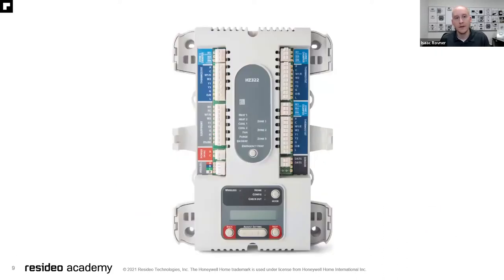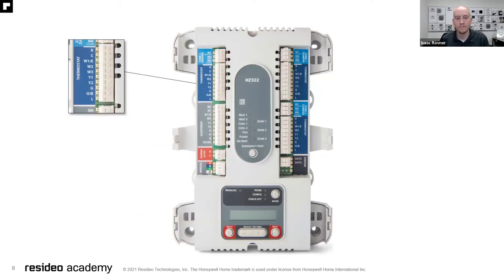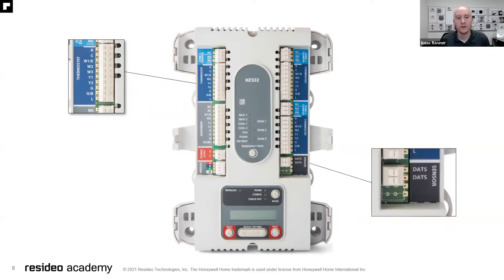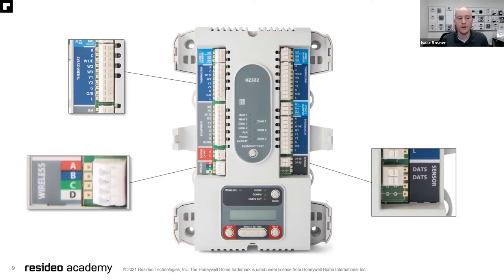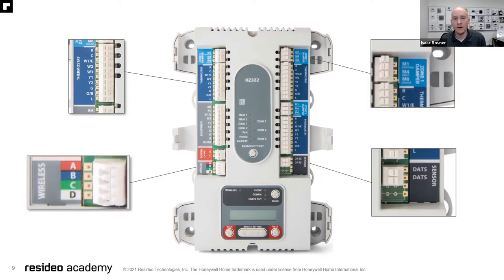Here we have our thermostat terminals — these are all dry contacts, meaning there's no voltage going out. You can easily wire in a smart thermostat since we have the C common terminal there. We have our DATS connection, which is used for our discharge air temperature sensors. Our ABCD terminals at the bottom left are used for our wireless control. Then our damper wiring is attached to each thermostat — the damper is clearly labeled by zone. Zone one damper and zone one thermostat are grouped together, and we wire the damper to whatever thermostat controls that particular zone.